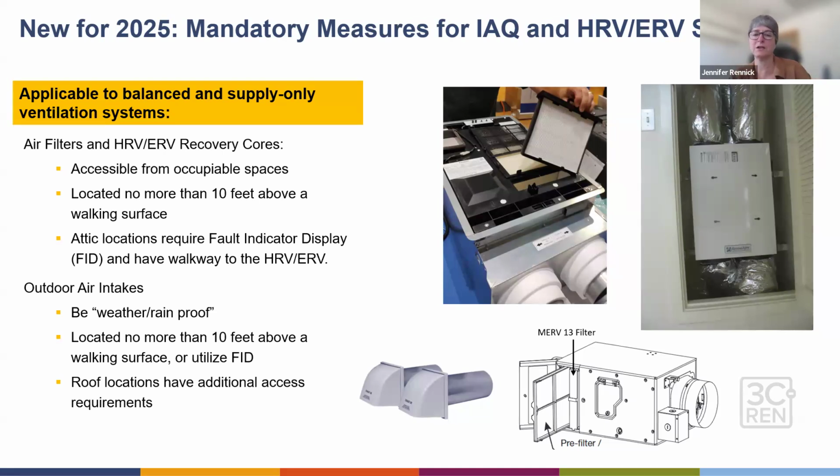That's what's nice about a heat exchanger, but the price goes up a lot more. But these are better ways. Balanced ventilation and HRV, ERV systems are better ways to meet the indoor air quality part of the project, because with just exhaust-only bathroom fans, which is the most common, least expensive way, we are counting on the wall assemblies, roof assemblies and the detailing around our windows and floors to be very leaky, right? Because you negatively pressurize the space.